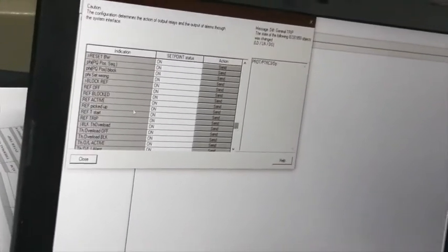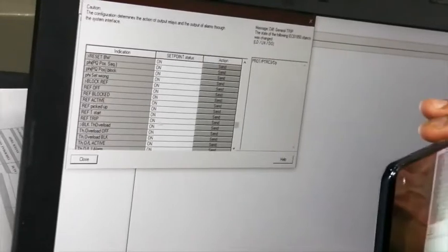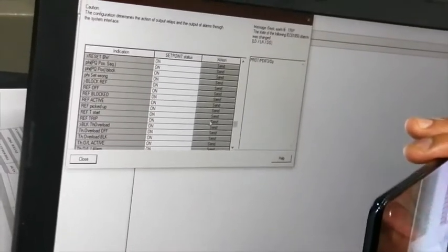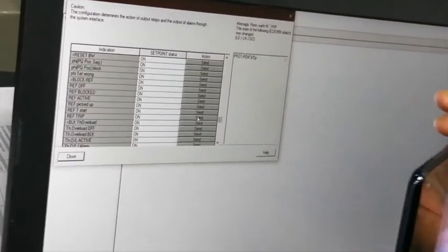I will show you how the engineer is forcing the differential trip. So now he has normalized the differential trip, and now he will search for the REF trip in the software. He has searched for the REF trip, and now he has sent it. Force the REF trip. First we will show you on the 11 kV protection.